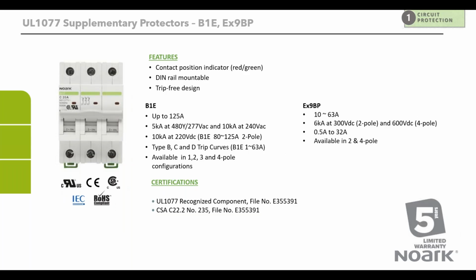We also have the UL 1077 supplementary protectors, which, like I said before, are backup protective devices, so they're not meant to be used as a standalone. You have to have a branch circuit breaker upstream of the supplementary protector. So we've got the AC/DC type, and also the fully DC type, which is the EX9 BP. These products are UL 1077 recognized, both for the US and the Canadian market. In terms of the features, it's the same as the UL 489 type: the trip-free design, DIN rail mountable, and the contact position indicator.